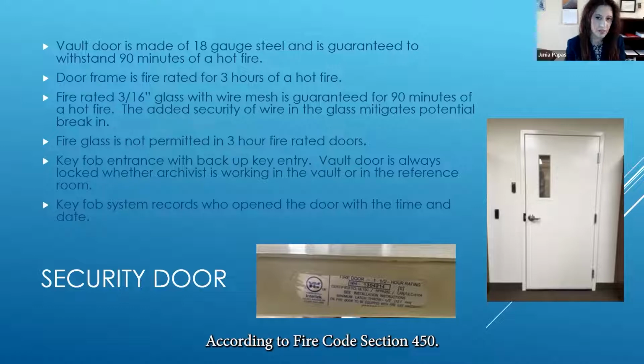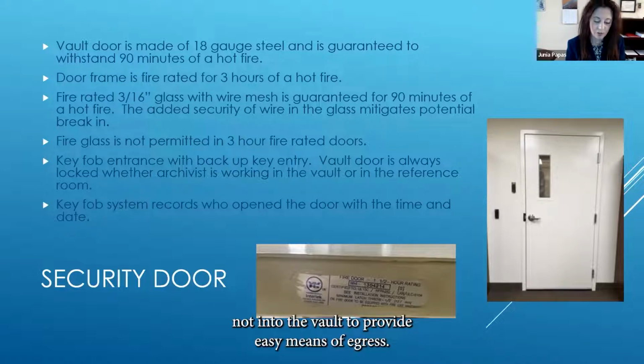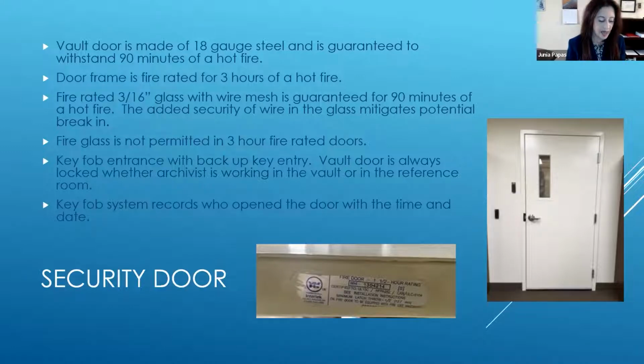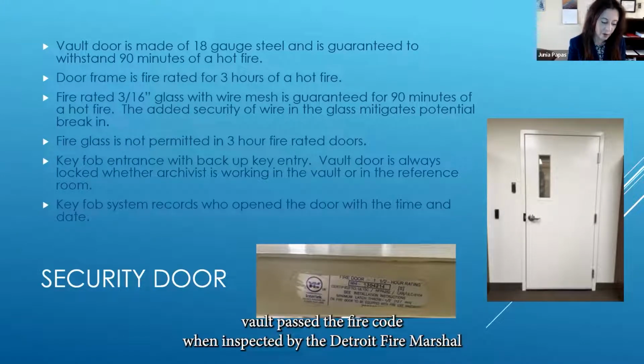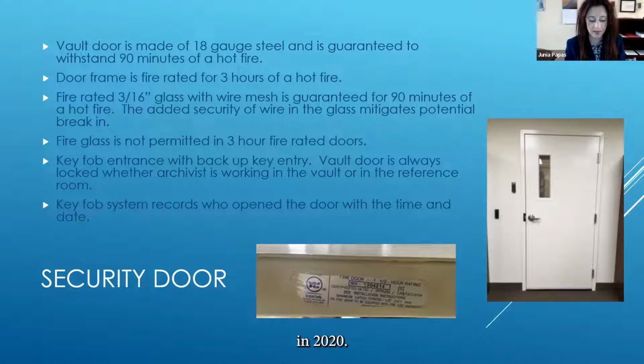According to Fire Code Section 450, an archival vault door must swing out of the vault, not into the vault, to provide easy means of egress. Our door swings out of the vault, so it is within these guidelines. Our vault passed the fire code when inspected by the Detroit Fire Marshal in 2020.